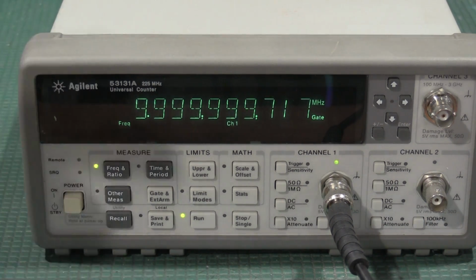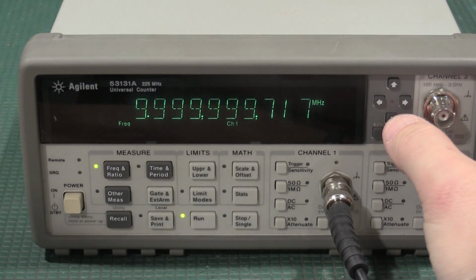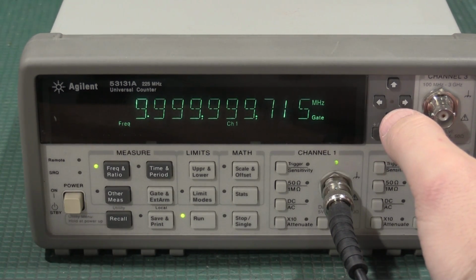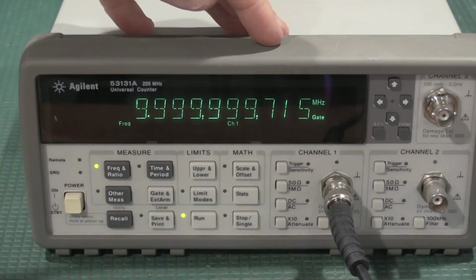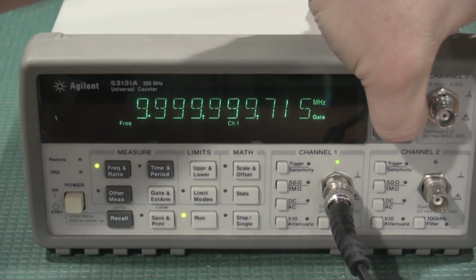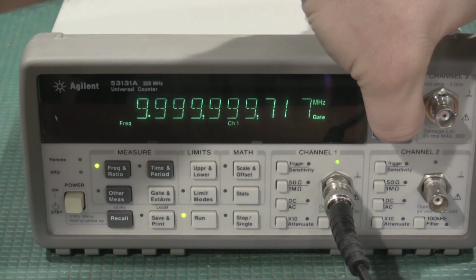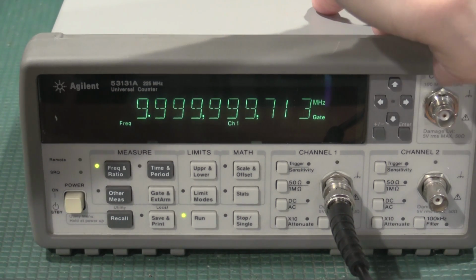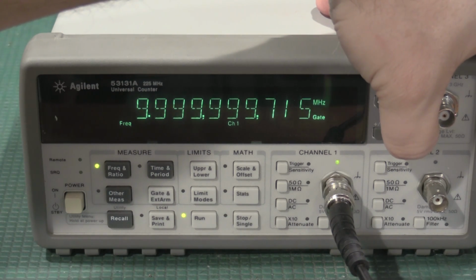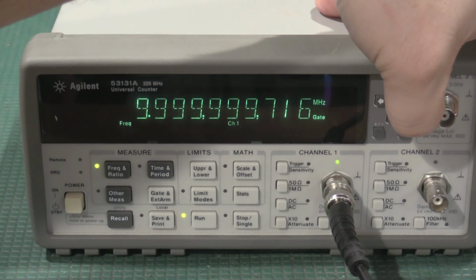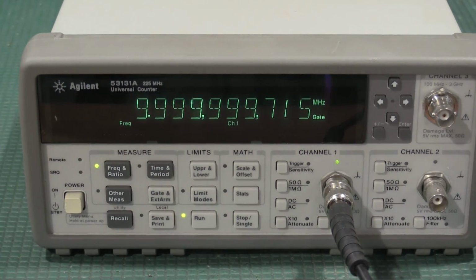Okay, we have come down significantly in frequency. So this means the internal oscillator is running a little fast. So what we're going to do is finish up the calibration. This is actually a soft calibration. It says all we're supposed to do is press one of the arrow keys. Oh, that doesn't work. So let's check the service manual.